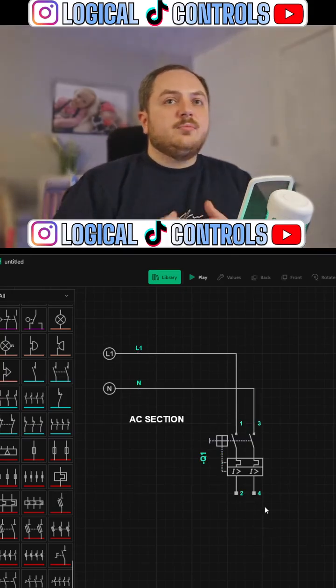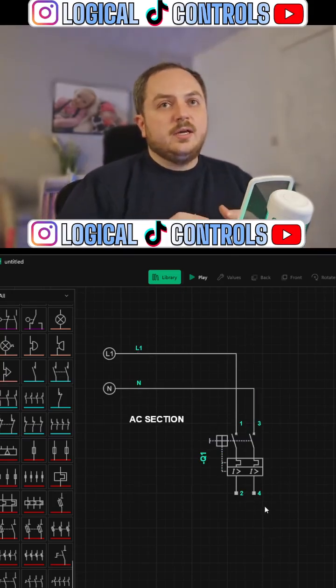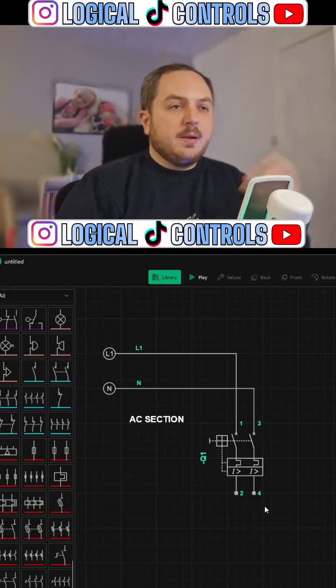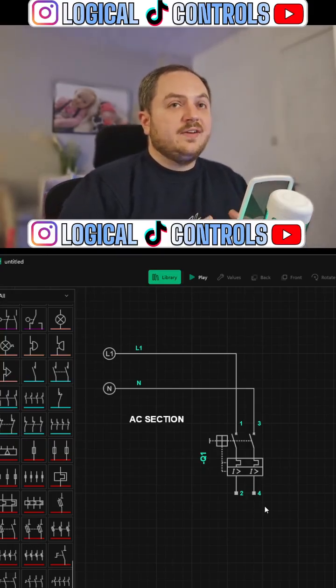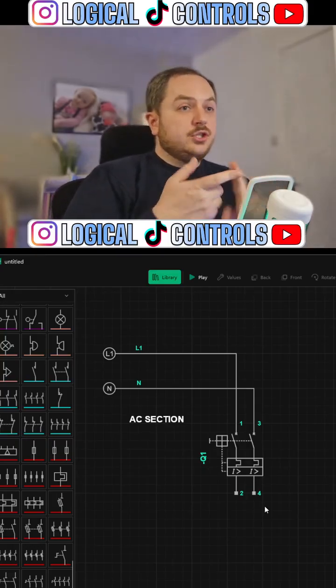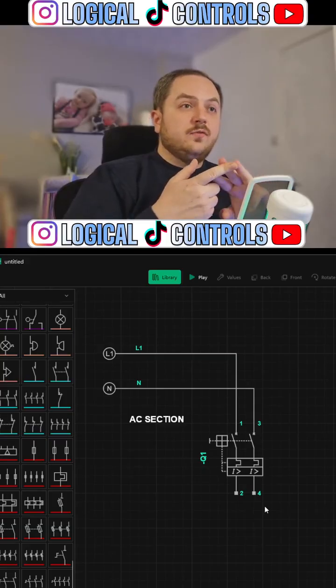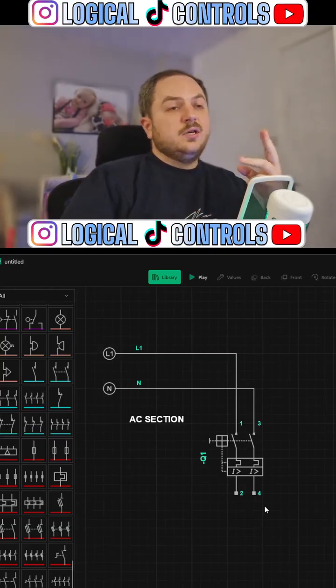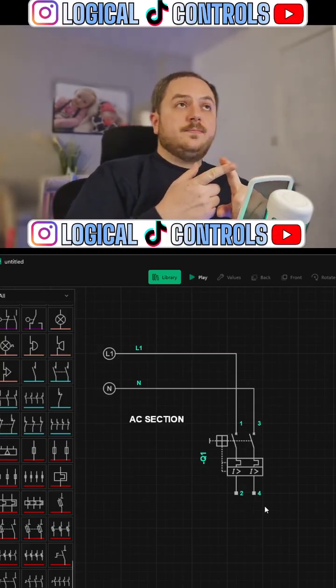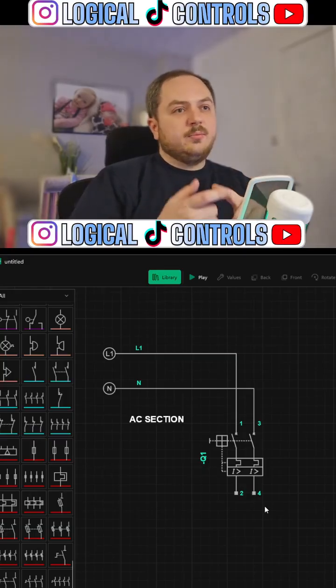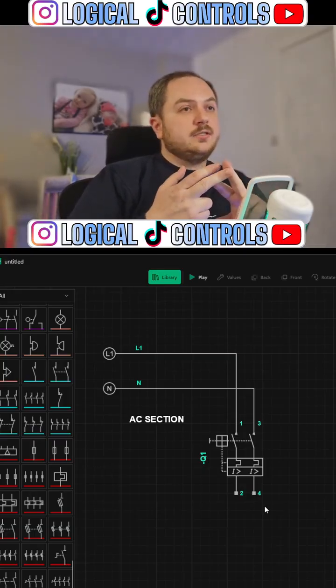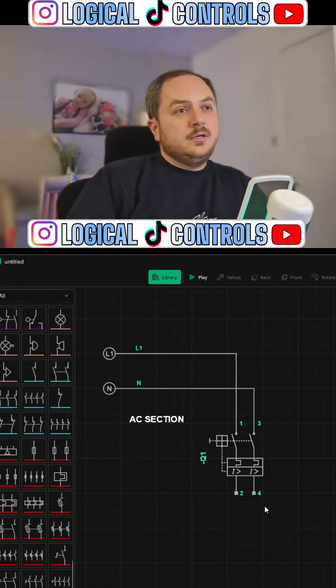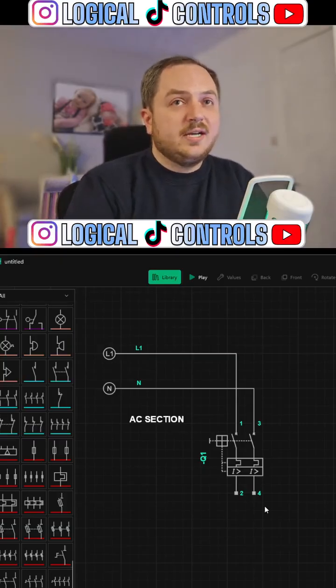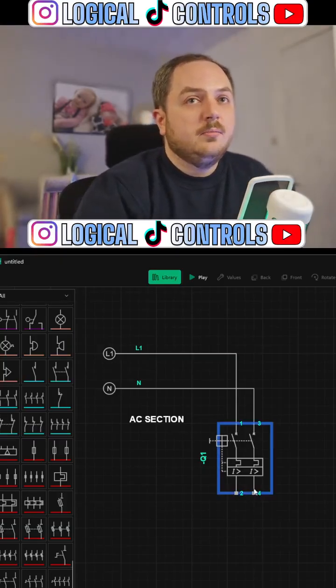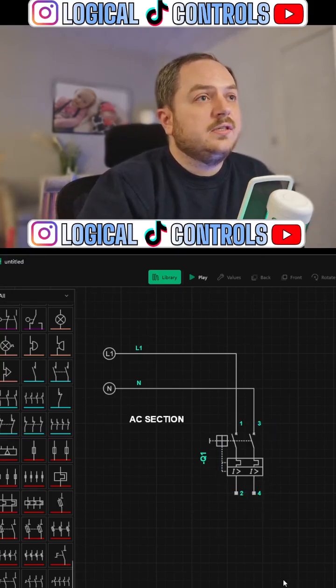So the ways you can protect a motor, or provide a supply to a motor - you can either have a circuit breaker, contactor, and overload, which requires 3 parts, or you can do a manual motor starter, or motor circuit breaker, and contactor, which is only 2 parts. So it's technically more efficient, space-wise in your panel, to do it the motor circuit breaker route with just a contactor.